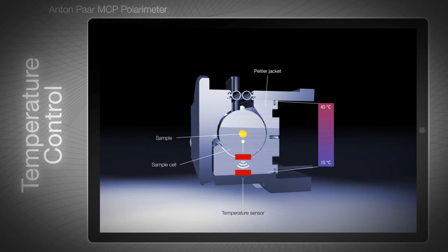In order to control the temperature in the most precise way, it also has to be measured very precisely. The temperature sensor is located inside the large thermal mass of the metal cell, very close to the sample. The position inside the cell avoids effects resulting from gradients and thermal antennae like filling ports, in which external dipping probes would be located.